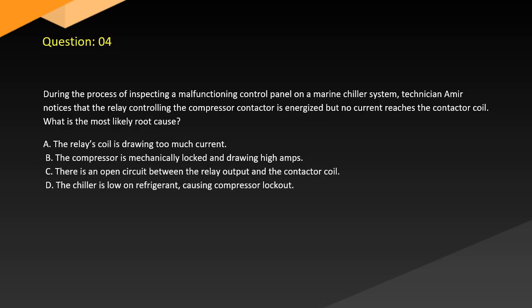Question 4. During the process of inspecting a malfunctioning control panel on a marine chiller system, technician Emir notices that the relay controlling the compressor contactor is energized but no current reaches the contactor coil. What is the most likely root cause? A. The relay's coil is drawing too much current. B. The compressor is mechanically locked and drawing high amps. C. There is an open circuit between the relay output and the contactor coil. D. The chiller is low on refrigerant, causing compressor lockout.